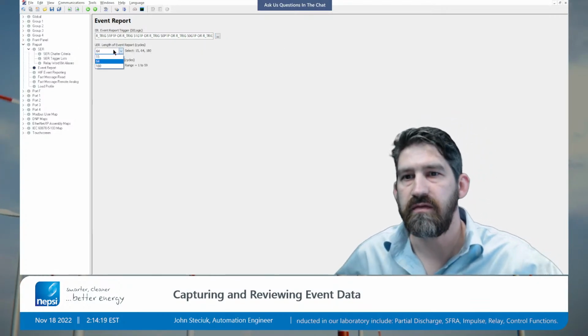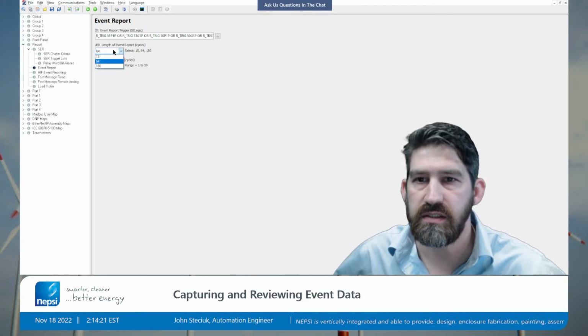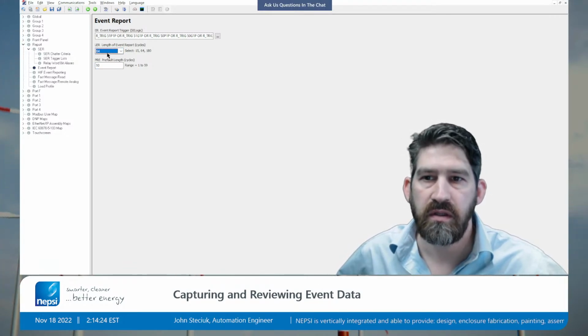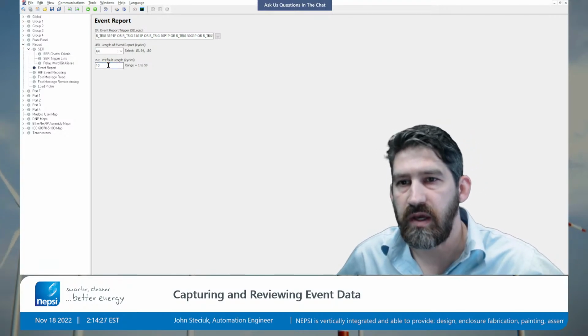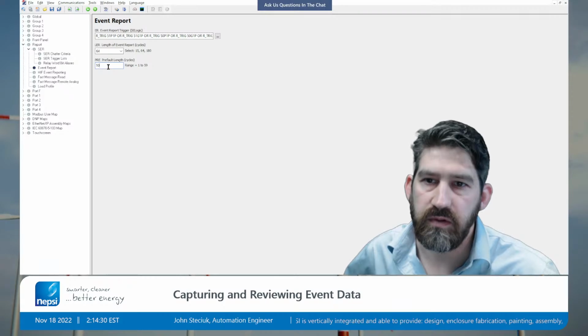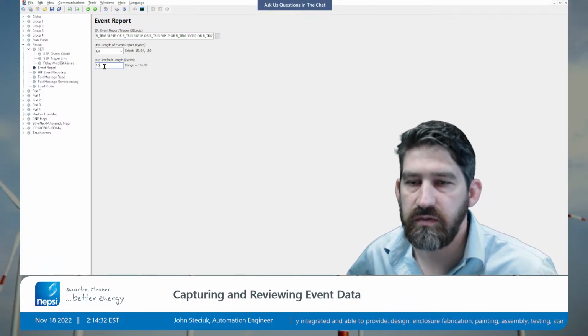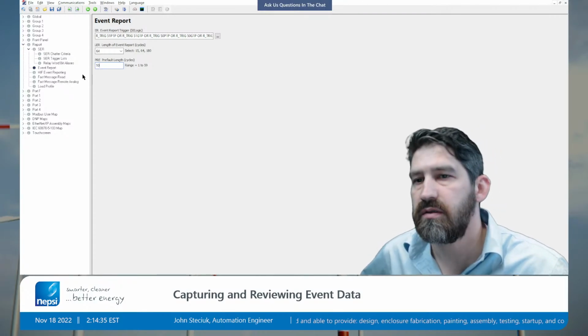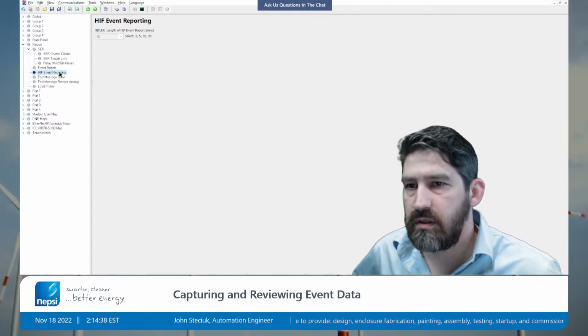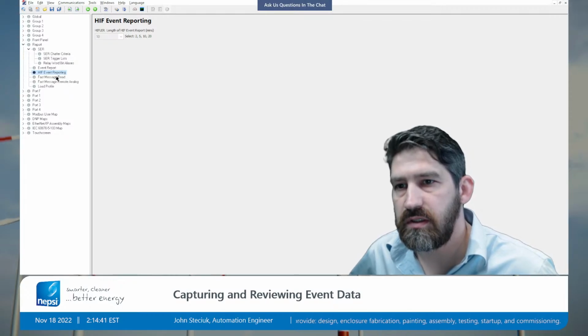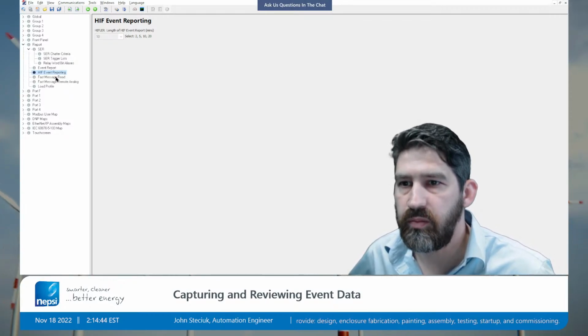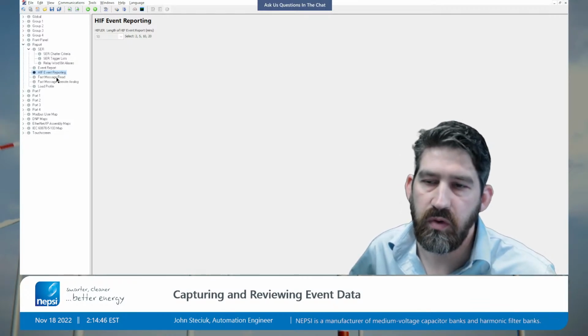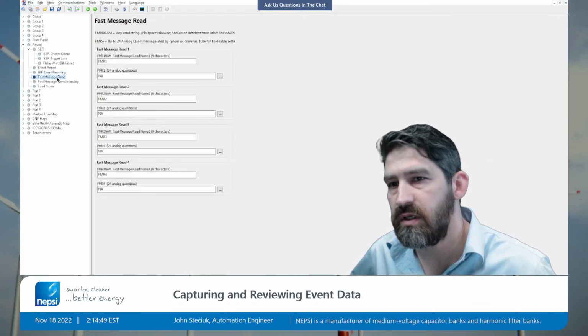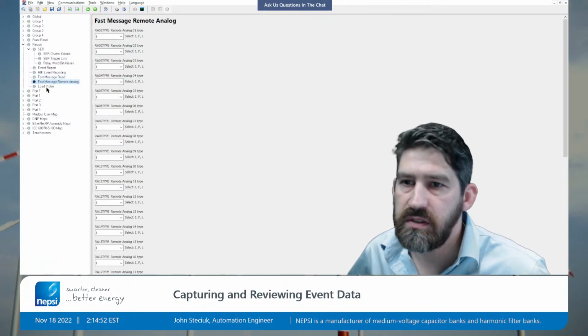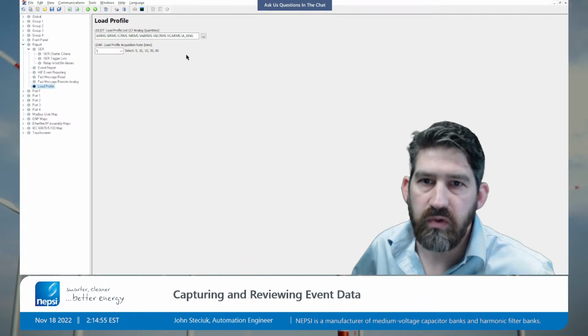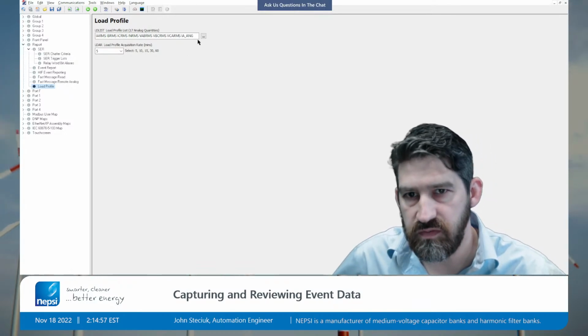The next setting is the length of event report, and you can choose either 15, 64, or 180 cycles. And after that, we have the pre-fault length. You can specify anywhere from 1 to 59 cycles to record pre-fault data. So there's some other settings that you can go through in the reports section. This is high impedance fault event reporting that you can enable, and they have some fast message read features. But I want to get into the load profile settings quickly because I find this useful from time to time.